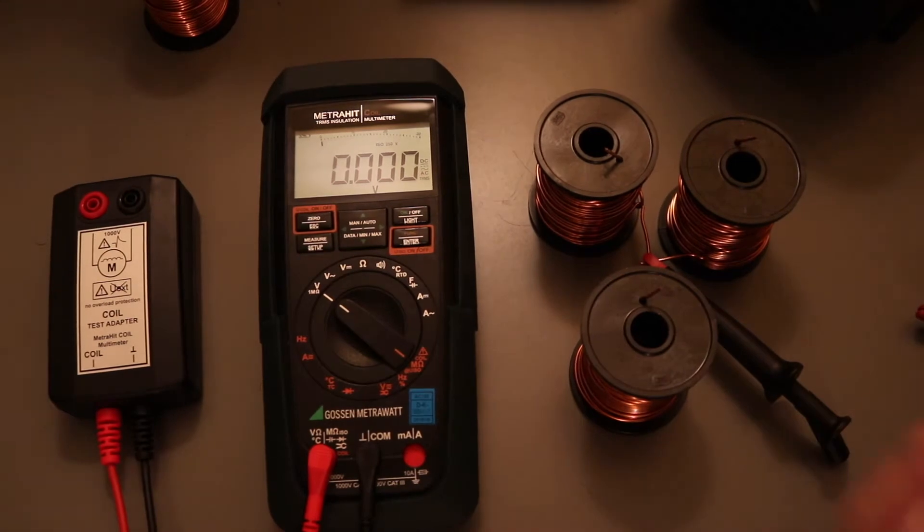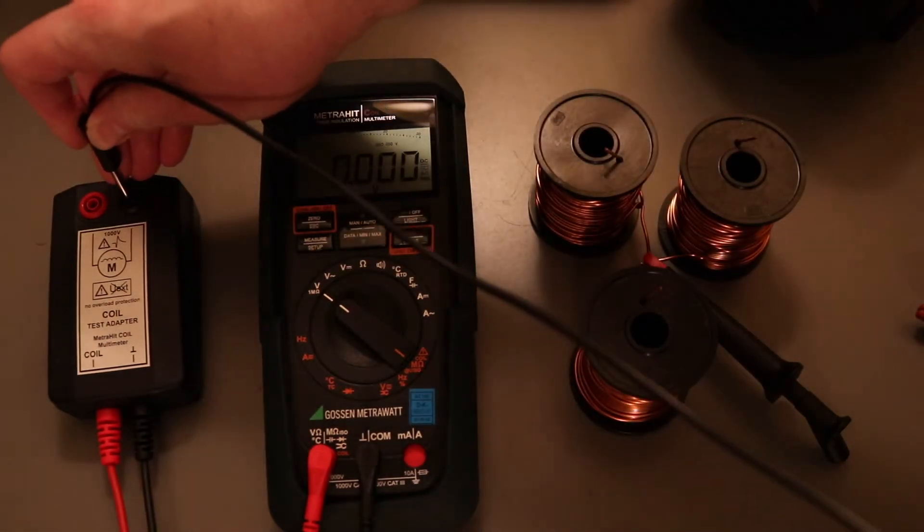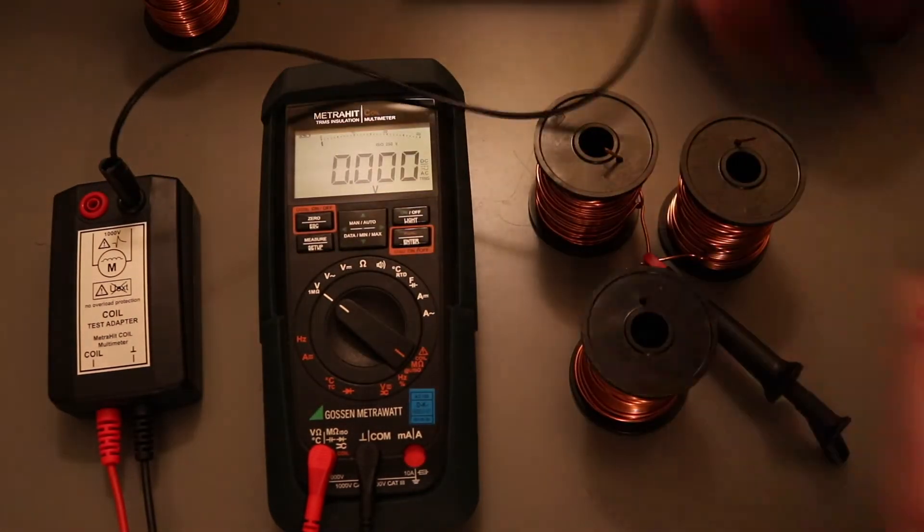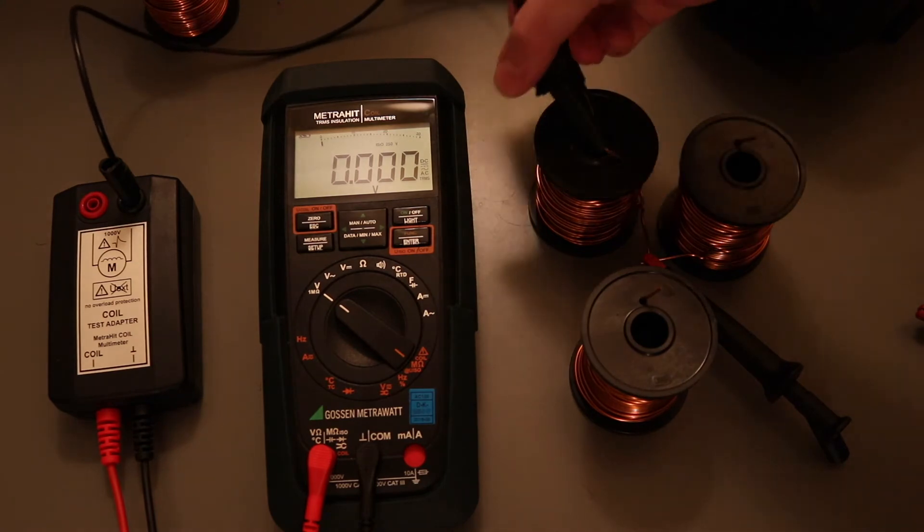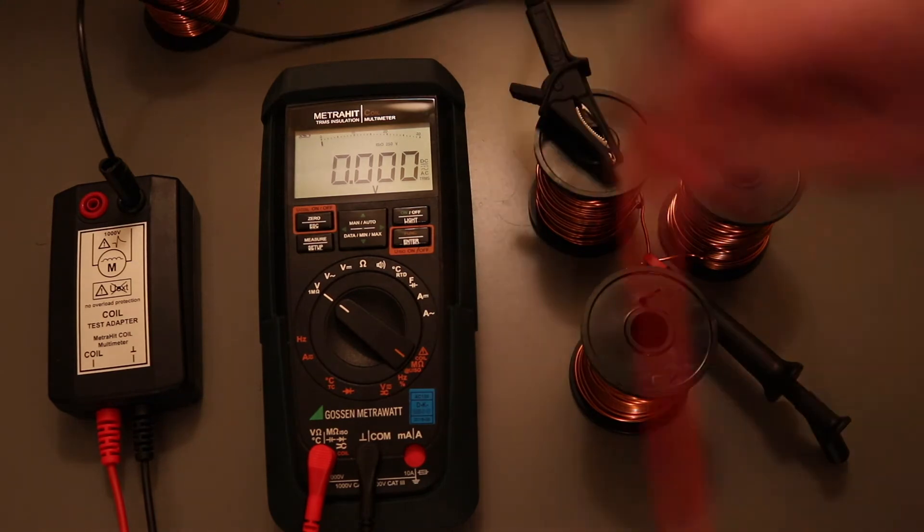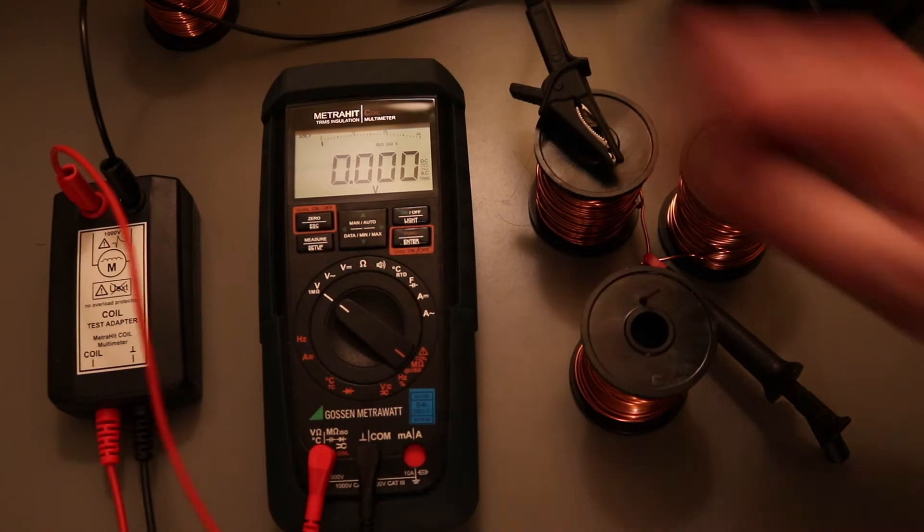OK, so the little motor that I have is too small a motor for this coil test function. So I would need around about a 15kVA motor to get this to read.